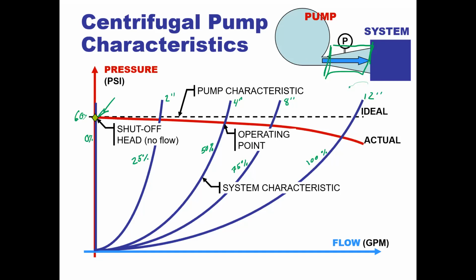But this is actually how you start a centrifugal pump. You start with your discharge valve closed, and then you'll slowly open it to 100%. So this won't damage the pump at all if you run it for 5 minutes, 10 minutes. I wouldn't run it for an hour, but 5-10 minutes won't damage the pump, as long as it's filled with liquid, you won't damage the pump.